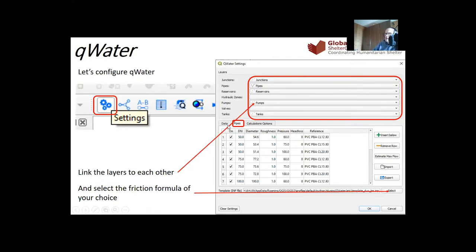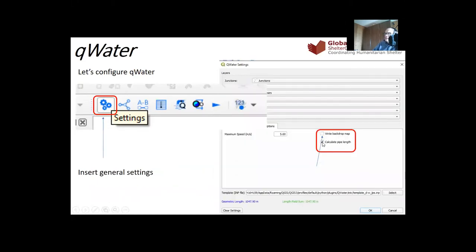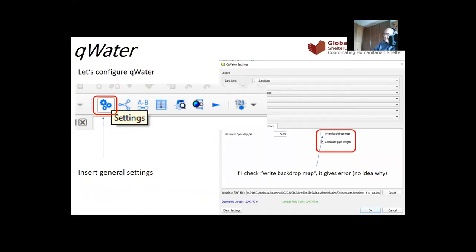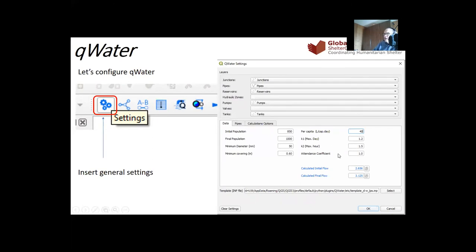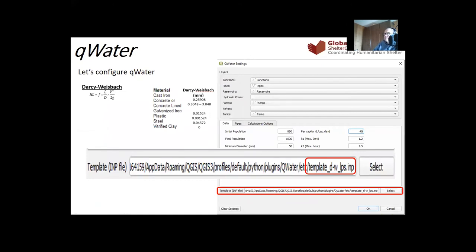Under Pipes, go to Data and click Calculate Pipe Length Automatically. Note: the Write Backdrop Map option does not work — it causes an error. Just leave it unchecked. I selected the Darcy-Weisbach formula with liters per second. You can also enter population information if you have it. If you choose Darcy-Weisbach, set the appropriate friction parameter — for plastic pipe, that would be 0.0015.